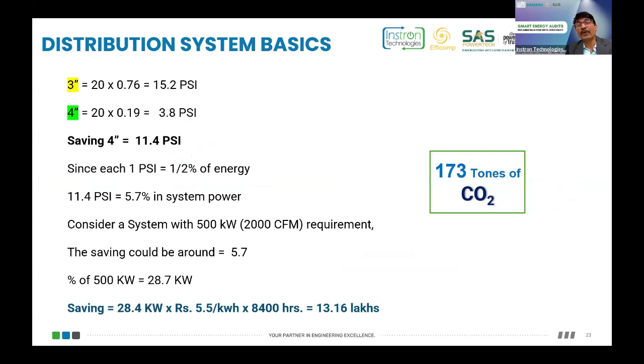But if you see the operating cost in a year, because we know smaller the line size, higher would be the pressure loss. So with a 3-inch line, there would be a 15 psi drop in a system, and with a 4-inch line, the drop would have been only 4 psi. So if a user at the end of the line requires higher pressure, then unnecessarily you have to increase the pressure at the generation at the compressor house.